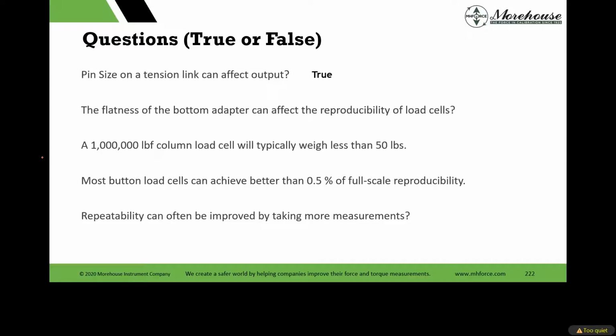The flatness of the bottom adapter can affect the reproducibility of the load cell. That was the multi-column cell example, where when I ground and used a flatter base, the number went from like 0.123 to 0.023. A 1 million pound column load cell will typically weigh less than 50 pounds. And then I got pounds wrong again. That's a pretty big load cell with 4-inch thread, probably not going to weigh under 50 pounds. But again, I should have clarified that with tension or compression, though a column load cell, not multi-column, can weigh a lot less than a shear web.